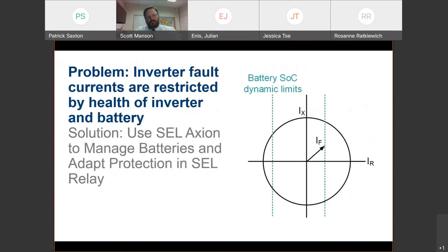Here's another interesting problem that has become very pronounced in low voltage microgrids, especially. If you're familiar with battery systems, they have not just a battery, it's actually many thousands of little batteries, in series and parallel together. And at any one time, some of those batteries can be out of service. Not only that, they could be damaged, a fuse could be out, a contactor could be out, a circuit breaker could be open. In fact, it could be cold outside.